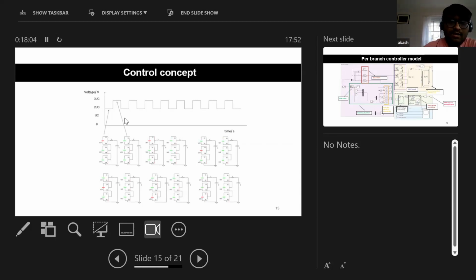So the idea is you have a baseline of two modules being on, and then you switch on a third module and PWM it, which takes you up to the 3 kilovolt level — that's how you balance it. Two ultracapacitor modules together give a voltage slightly less than 3 kilovolts, and when 3 are on, it gives a voltage slightly above 3 kilovolts. Over time, with high switching frequencies, that balances out to around 3 kilovolts.